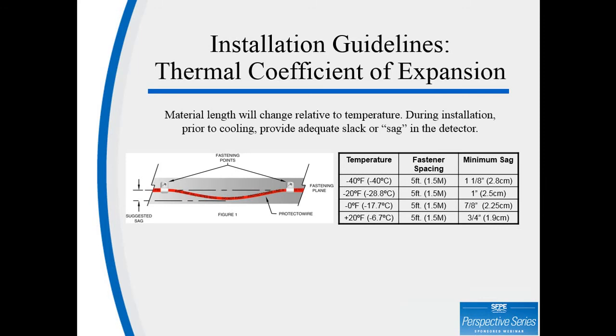But once that building is enclosed and ready to go, they start turning on the cooling units, and it may go down as low as 20 or 30 below, which will cause the detector to contract. This chart basically gives the designer a guideline as to how much slack to leave in the detector so that when it does go from one temperature to a much, much lower temperature, that slack will be taken up.